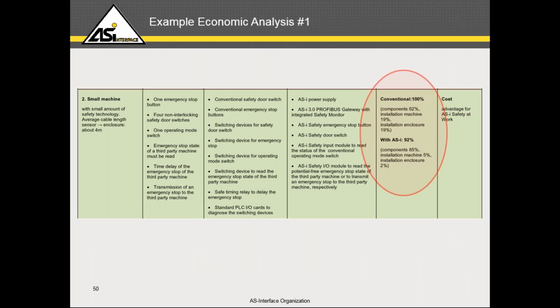So when we look at the cost perspective, the ASI, the engineering and time sums up to all with the cost. And when a small system is required, and the length of the cable from the sensor to the enclosure is 4 meters or so, it is still advisable to use ASI, as there is at least 8% saving compared to the conventional way of doing things.